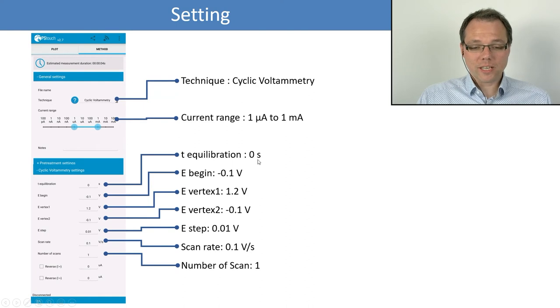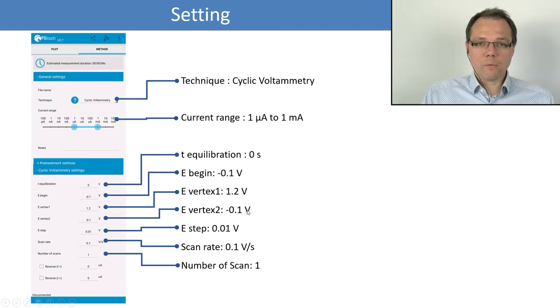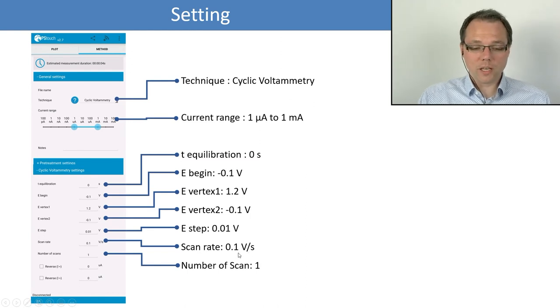Then we have an equilibration time, a waiting time of 0 seconds, which makes the measurement a bit quicker. We begin the scan at minus 100 millivolts, go up to 1.2 volts, and then turn again at the second vertex potential, where if we made multiple scans we'd flip again. However, we're just doing one scan. As a scan rate, how quickly we change the potential with time, we'd be changing it at 100 millivolts per second. This is everything we need to perform this experiment.